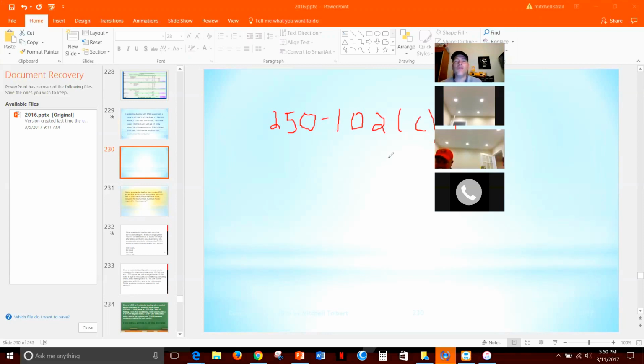Okay. So on page 124 is where we're at. It's a table that looks really eerily similar to the 250.66, which is on page 121. So I want you to look at page 121 first, and then keep your hand there on page 124. And let's just compare these two tables real quick, right? They look a lot like the same table, but the big difference between .66 and the new table is that we used to use .66 to size the neutral conductor.